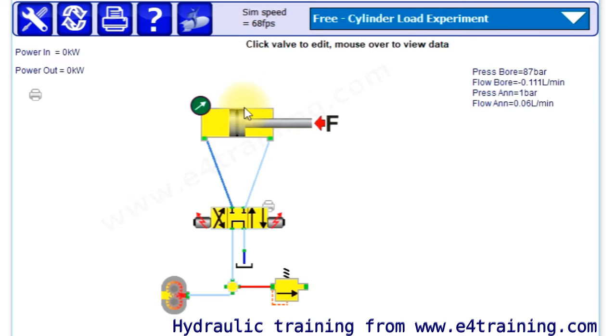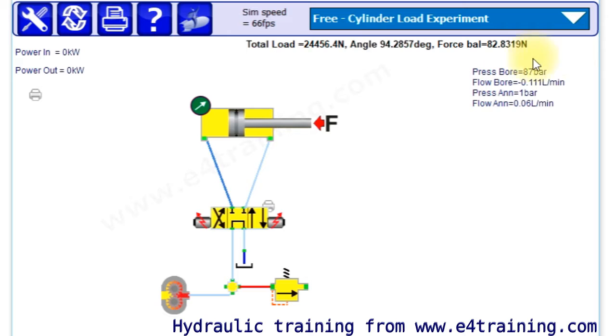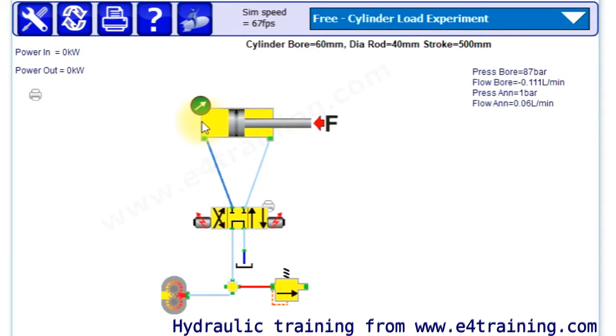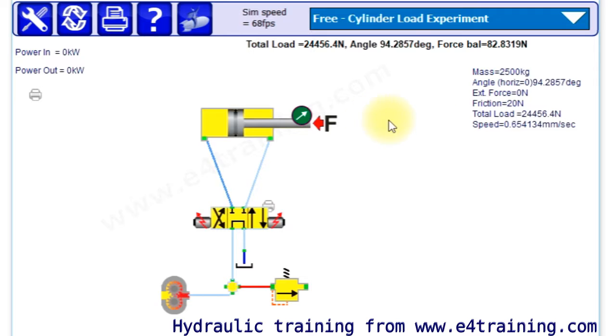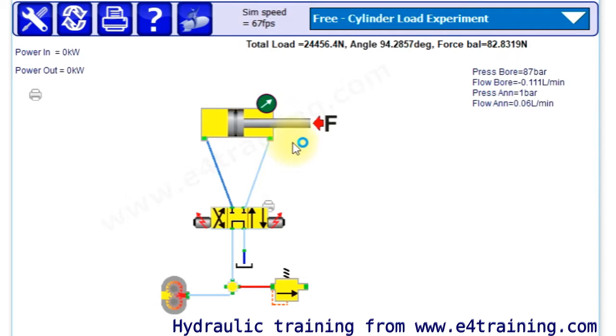We can see now we've put some pressure on the bore side. We've got our values here, so we've got pressure in the bore and this flow, and the cylinder is actually moving. We can see the speed if we move our indicator, our test gauge, to there. What's happening now is the cylinder is gradually creeping one way.